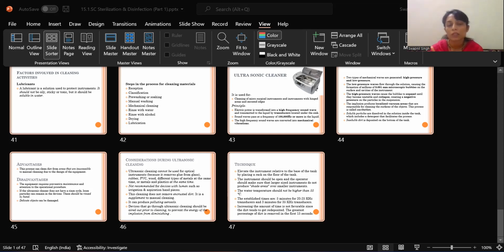Now, the agents mainly used are firstly water. Water that contains dissolved minerals such as calcium, chlorine, magnesium, and phosphate is known as hard water. When boiling this type of water, the aforementioned minerals will be deposited inside the washing wall and sterilizing container, forming a layer known as plaque. More energy will be consumed when dealing with such water. Water that does not contain minerals or only has a small number of them is known as soft water and is hence recommended for cleaning purposes.